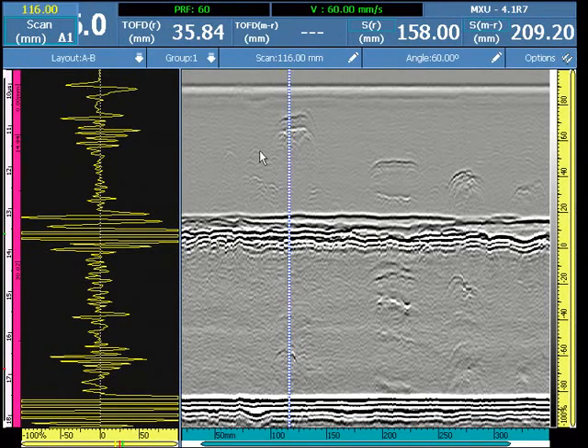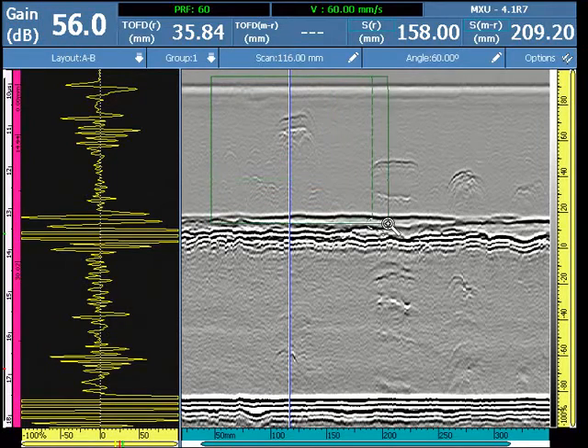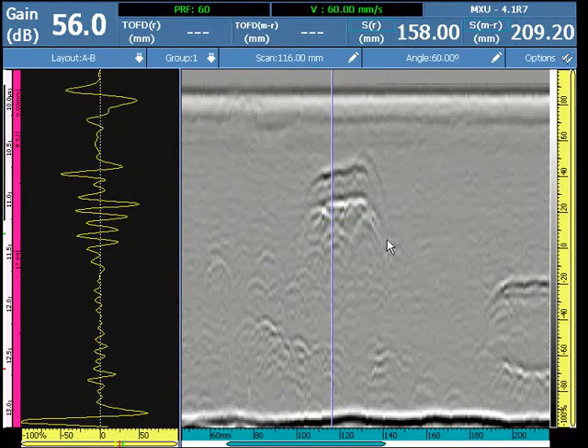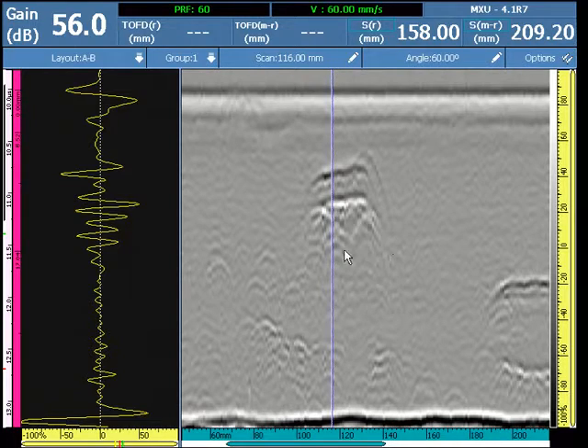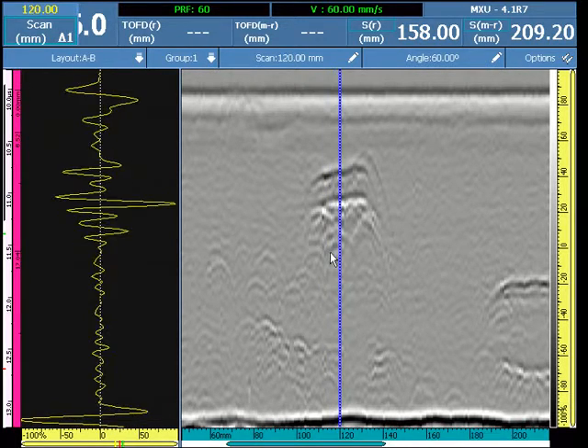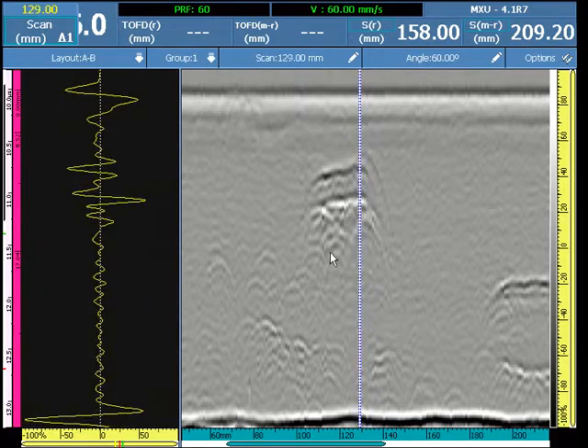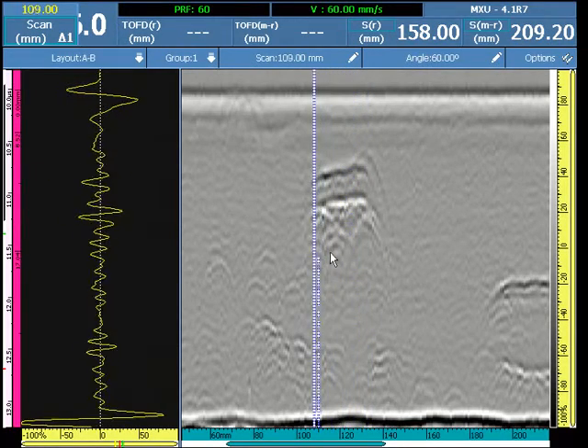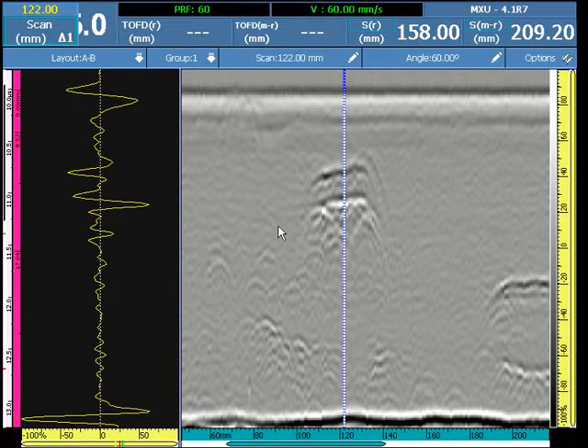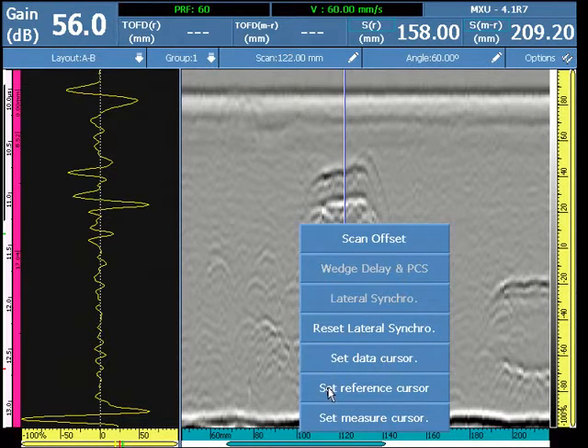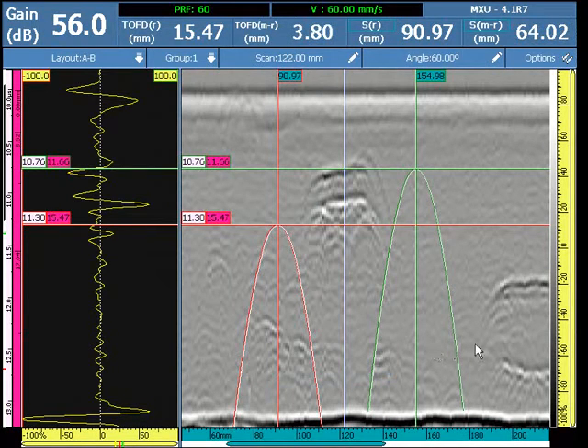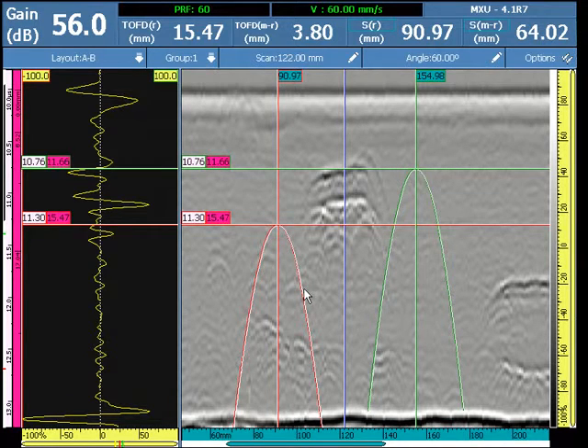We'll zoom in on this area using the touch screen — press and hold, drag your finger, and zoom in on the indication. We will select the data cursor and look at the indication in the A scan. Press and hold and set the red reference cursor and the green measure cursor on the display. As you can see, we have the parabolic cursor shapes that become visible upon calibration.